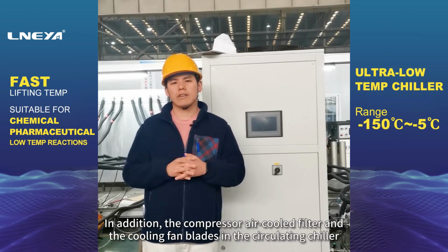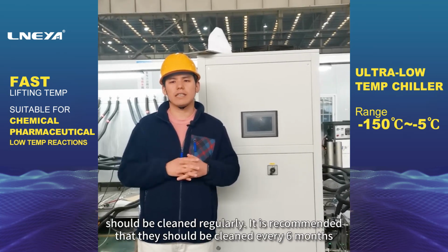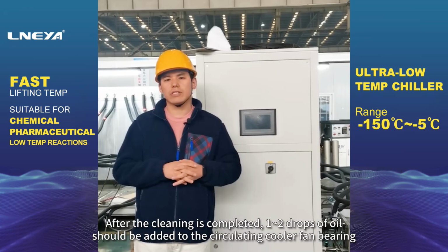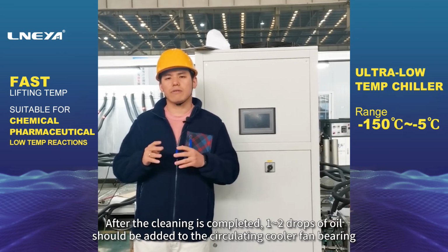In addition, the compressor air-cooled filter and the cooling fan blades in the circulating chiller should be cleaned regularly. It is recommended that they be cleaned every 6 months. After the cleaning is completed, 1 to 2 drops of oil should be added to the circulating cooler fan bearing.